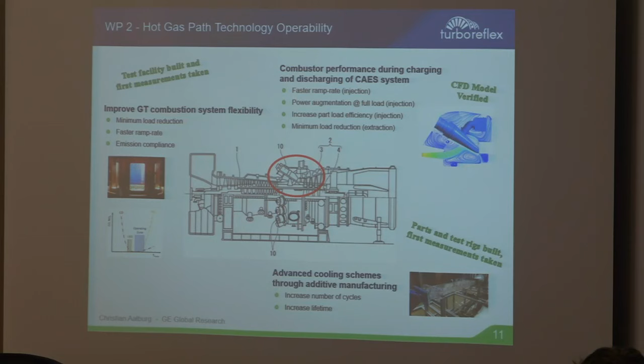A third element is mechanical integrity in flexible operation. We don't yet have so much information or understanding of how the material behaves under extensive thermal cycling, so there's a lot of conservatism applied in the design space today. If we understand this better, which is what we're trying to achieve, we can take out some of that conservatism, enabling faster ramp rates and a higher number of cycles. If we understand how cracks are not only initiated but also how they propagate, that can give us more room to operate.